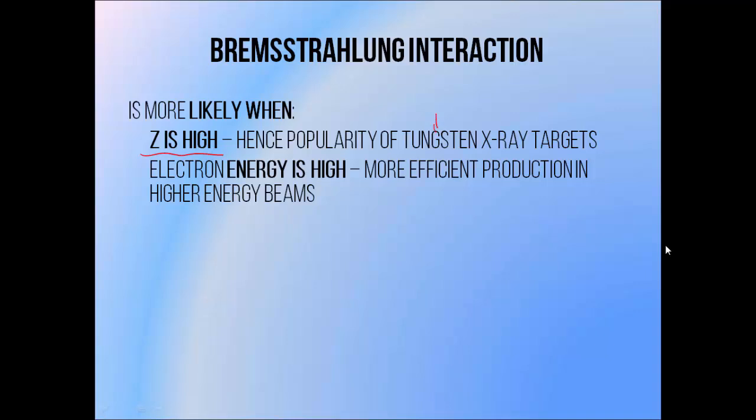You may wonder why we use tungsten instead of lead, which has an even higher atomic number. That's because while tungsten may not have as high an atomic number as lead, it is much more durable, so it is able to cope better with the stress of being exposed to a higher intensity beam of electrons. The interaction is also more likely when the electron energy is high, so the production of X-ray beams is much more efficient when higher beam energies are used. This is why when using a CT scanner, for example, if you increase the peak beam energy, your patient will receive a higher dose rate even if you use the same beam current.